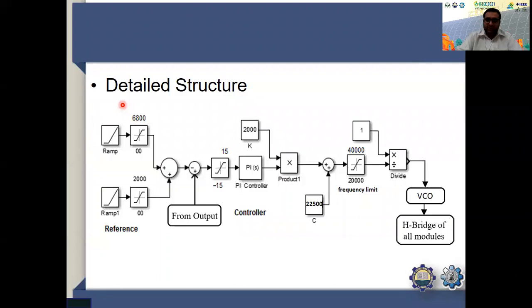Here is the detailed structure of the control that we want to implement. In this first part, we are comparing the output voltage with the input reference, where we have two blocks of 6,800 and 2,000. For the first step of 6.8 kilovolt, only this stage will be working, and for the next stage, the steady state operation, when our output voltage will be at 8.8 kilovolt, both of these will be generating the reference of 8.8 kilovolt that will be compared with the output signal, and an error signal will be generated.